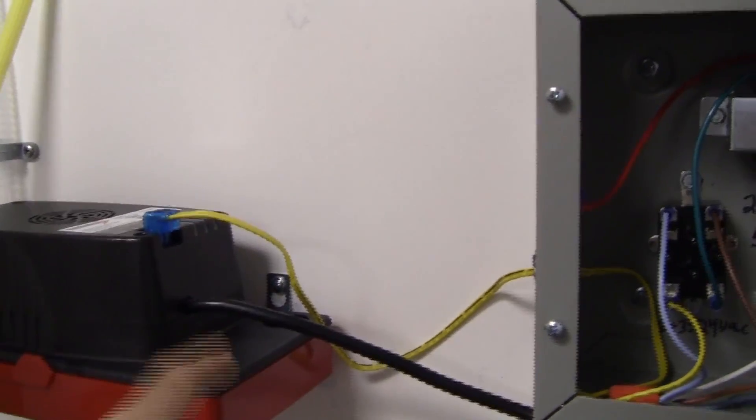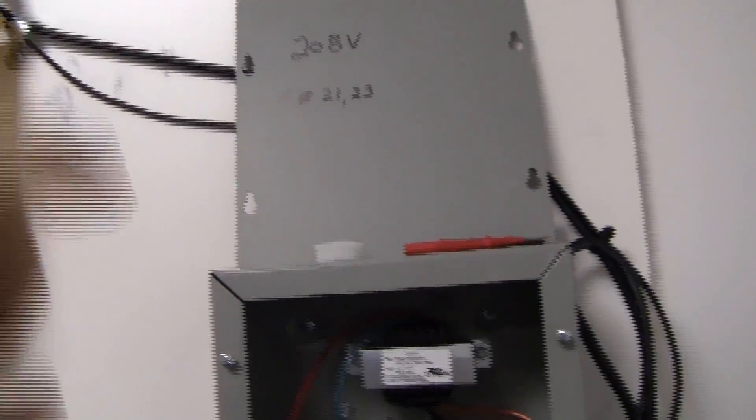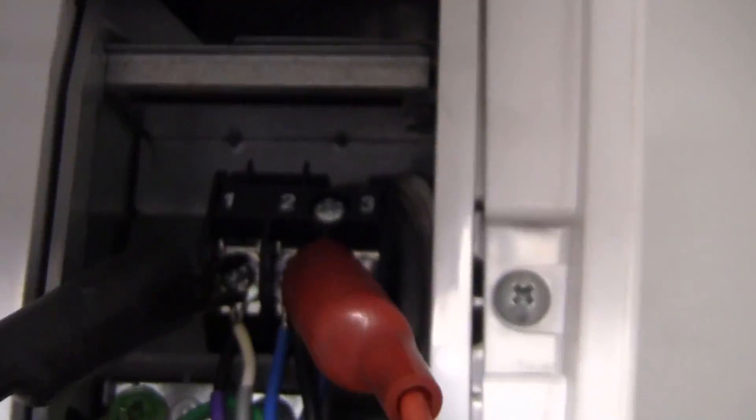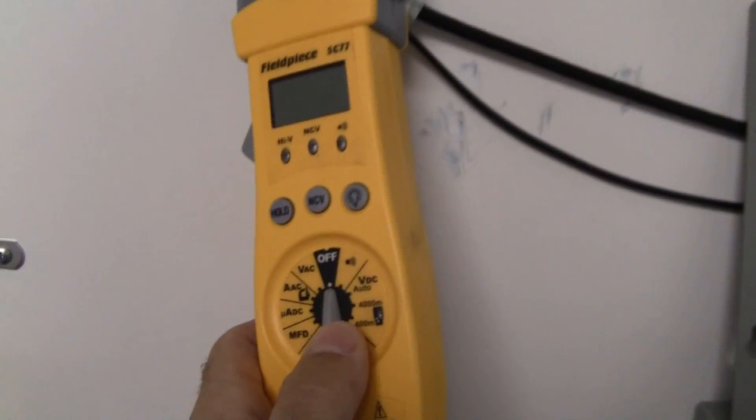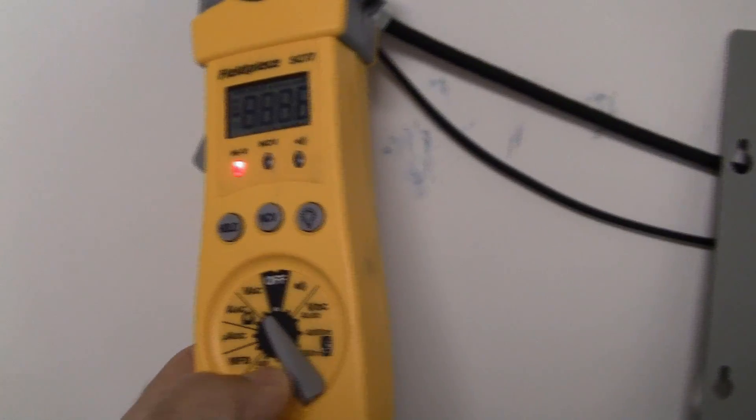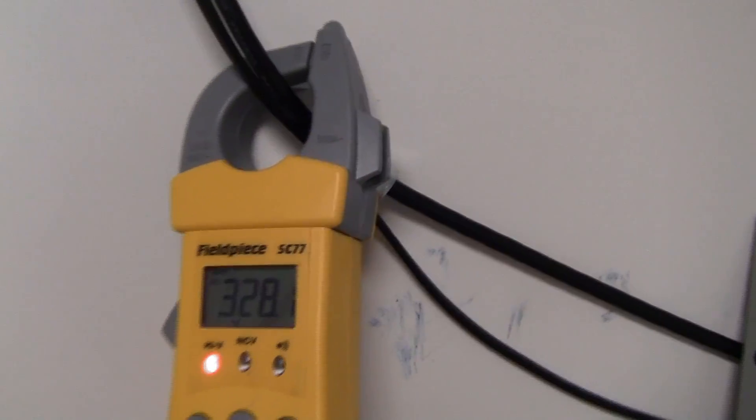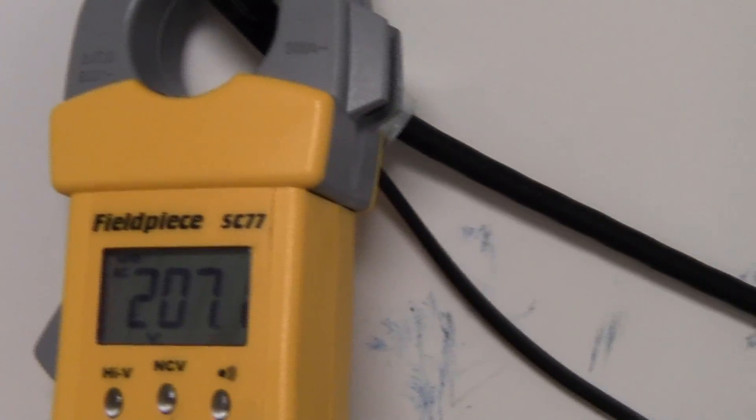I got the breaker on there's an LED light right there telling you that I got the power on to the evaporator and I put on my Fieldpiece leads on lines one and two. I'm going to turn the meter on voltage AC and you'll see that we have 207 volts.